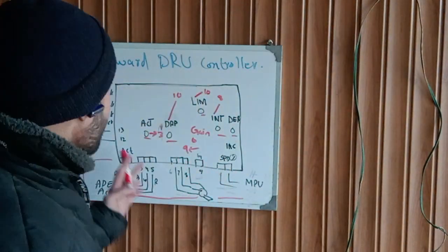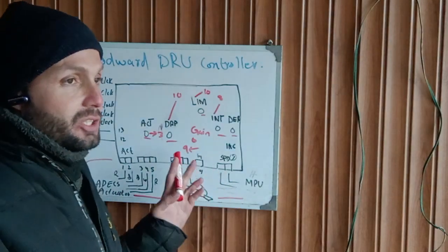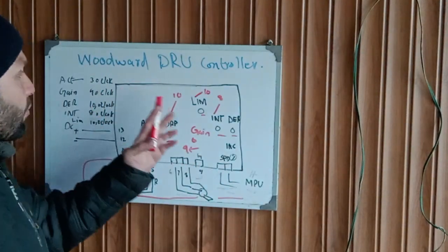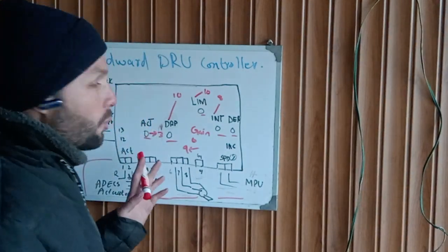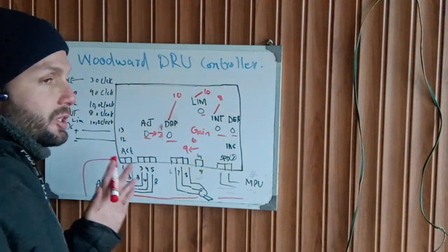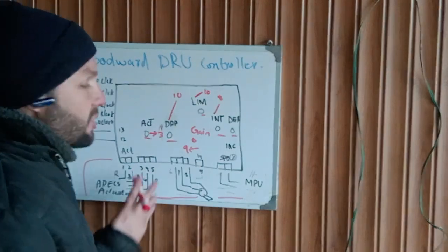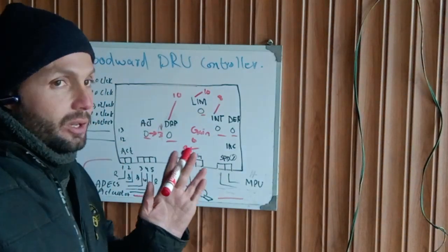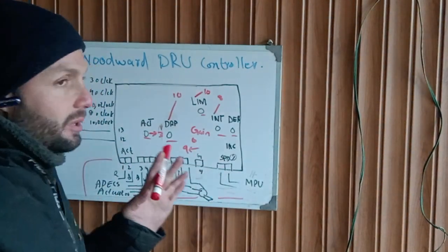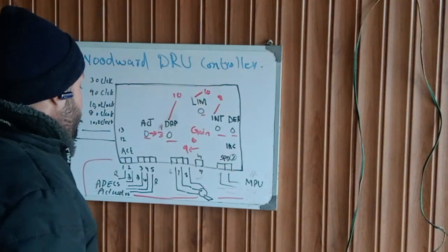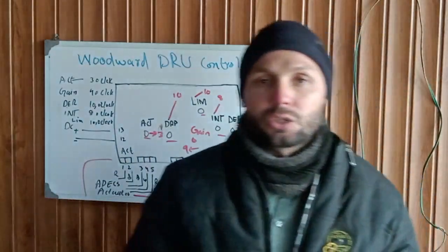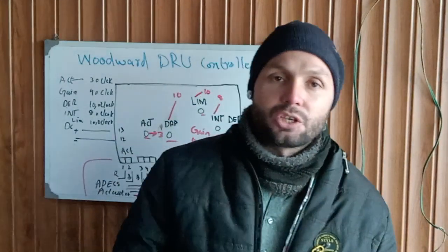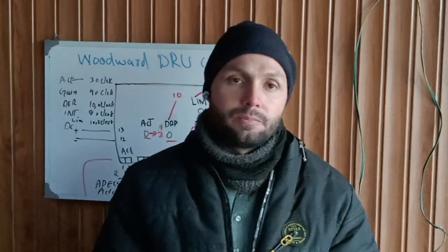It works digitally and performs the operation of our engine to match the speed of the engine with another engine, match the frequency, and match the output voltage of every single generator. These are all connected to each other to control the synchronization of parallel generators.